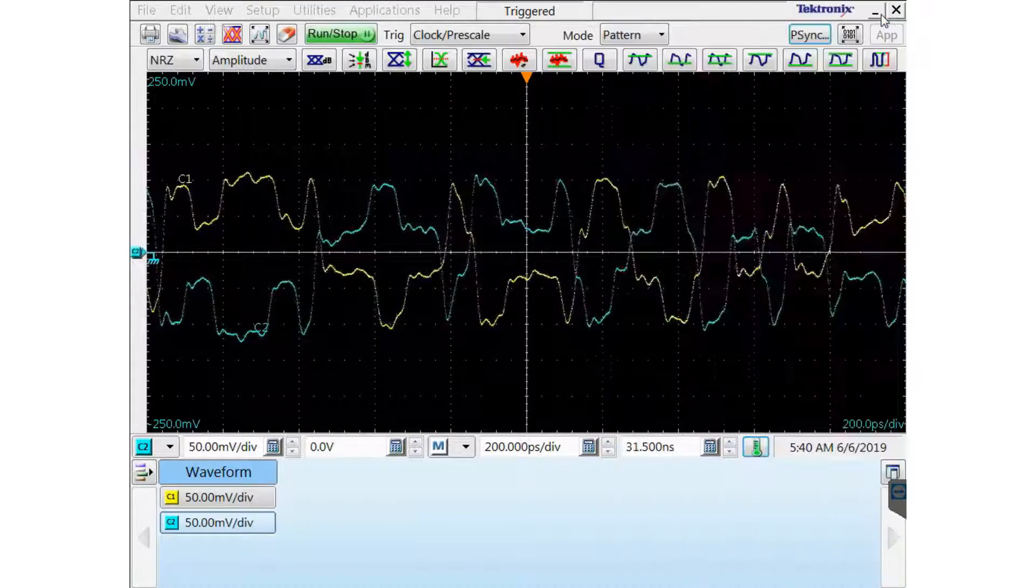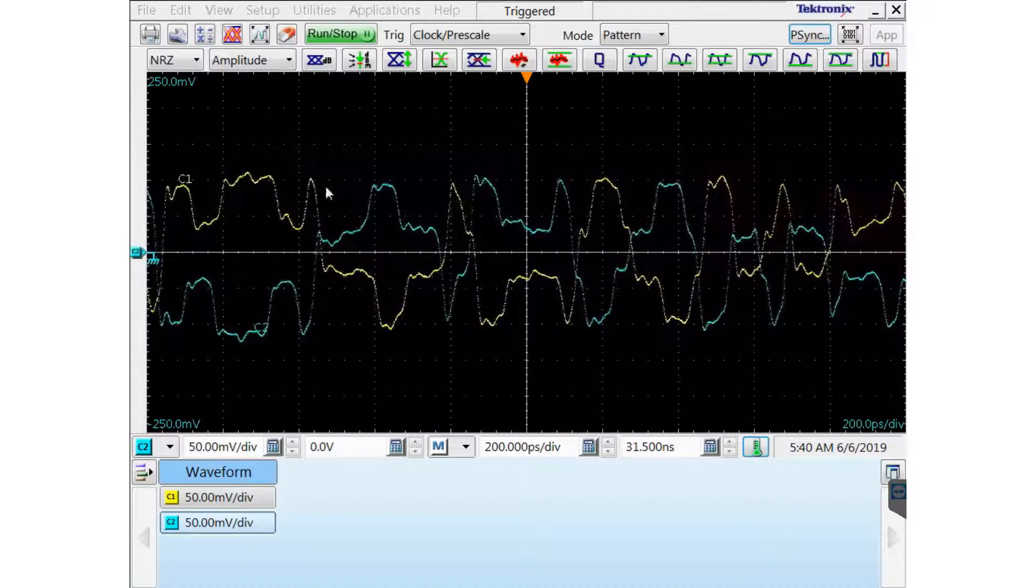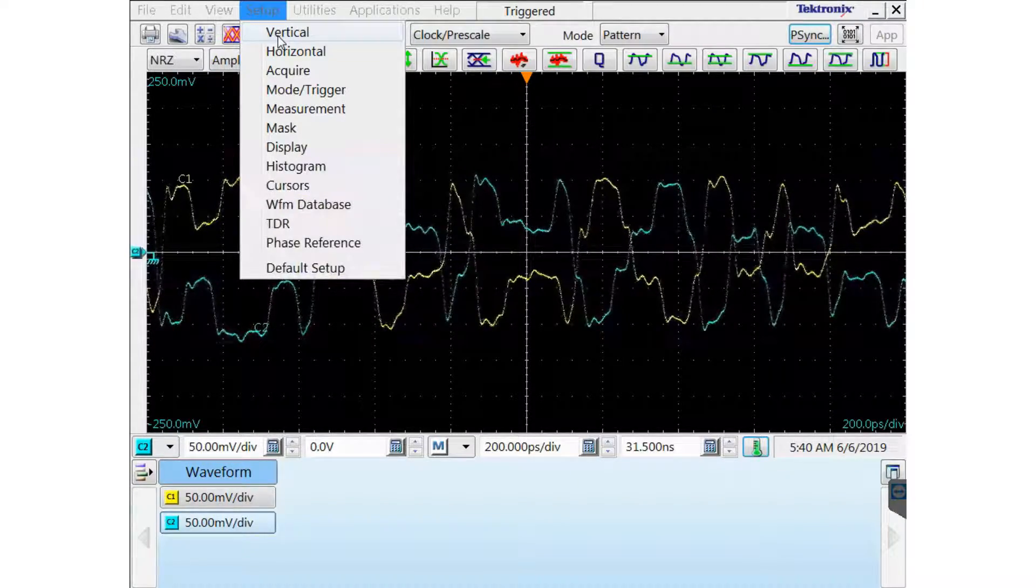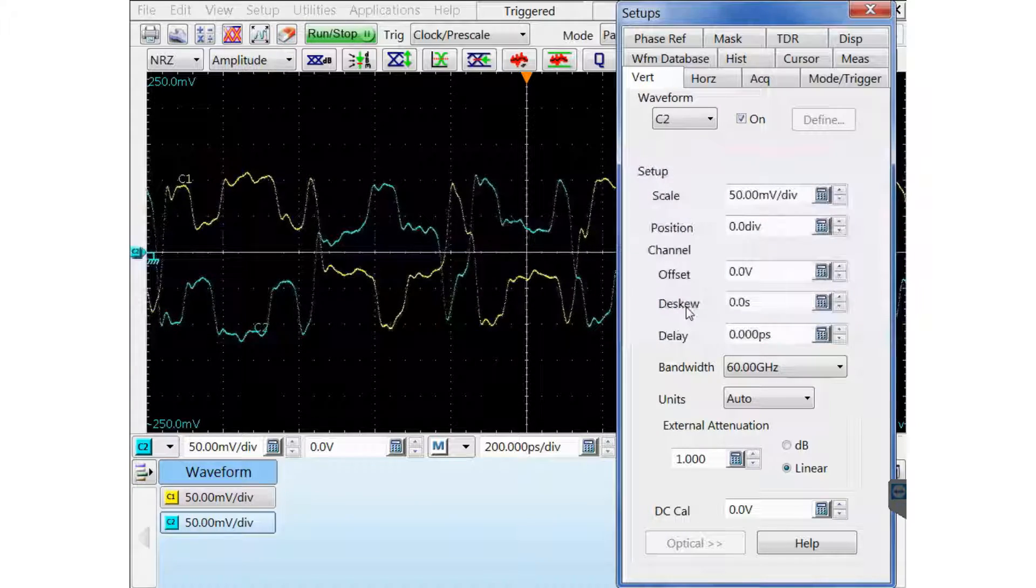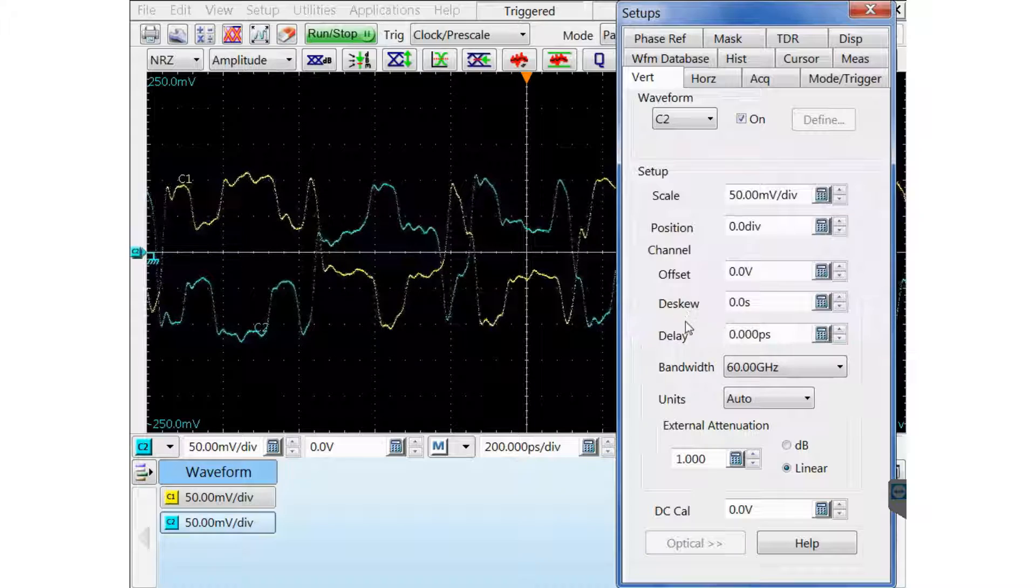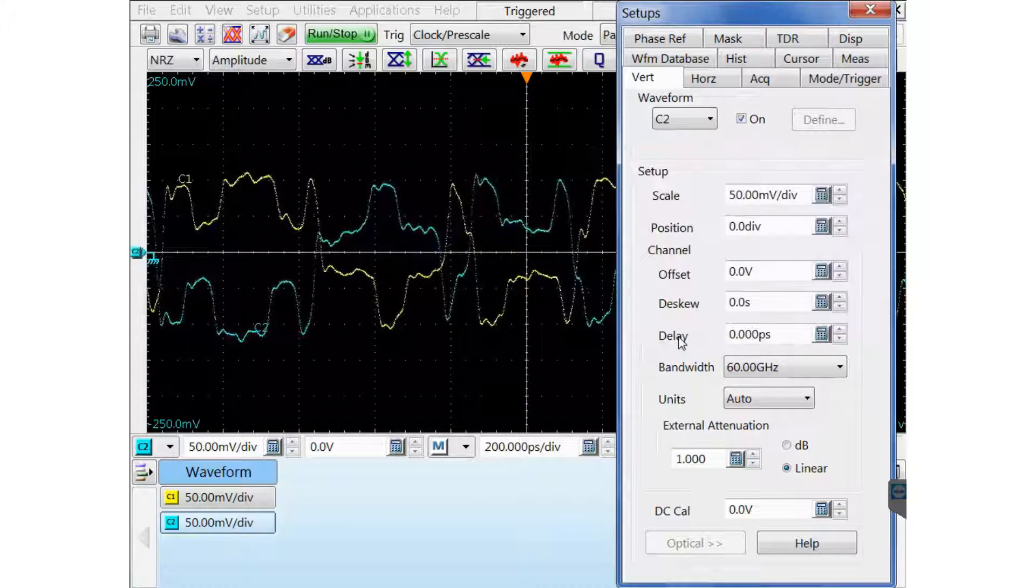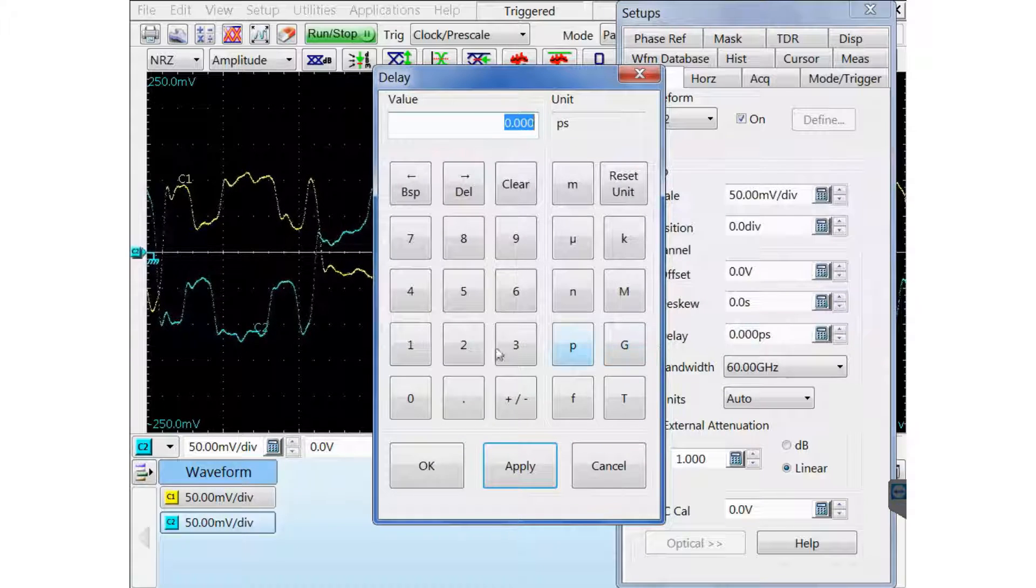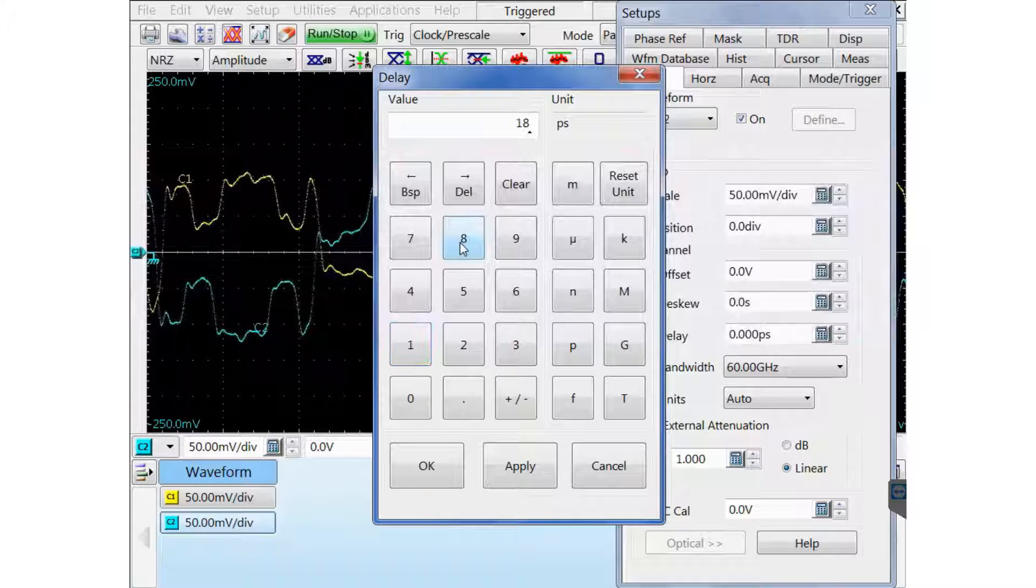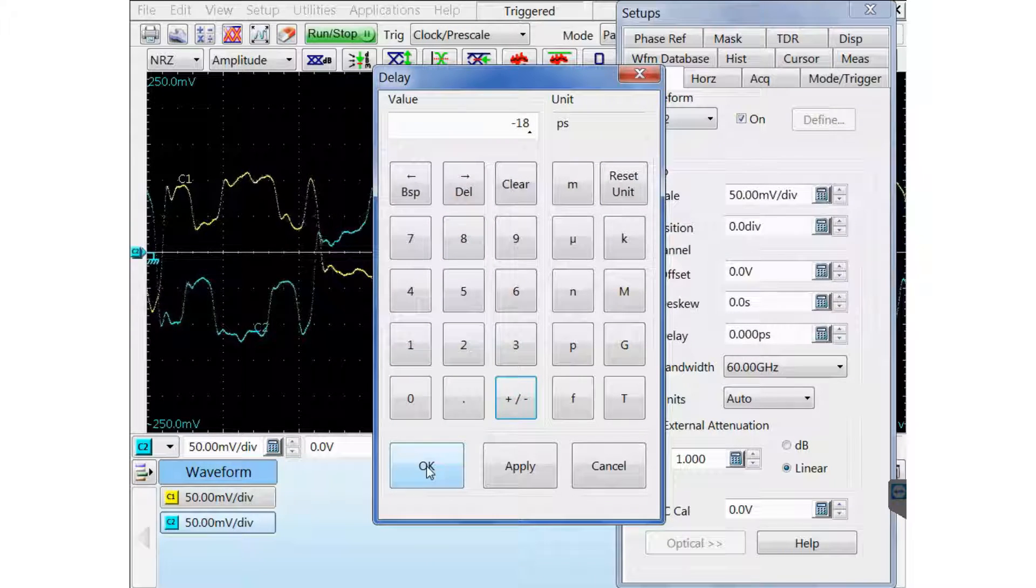I'm going to turn those cursors off. And then I'm going to enter the delay value in the vertical menu. There's the box called Delay. This is where you enter the value of the skew that I found in my coarse adjust. So I'm going to click on the button to enter the value, 18 picoseconds, negative, and click OK.